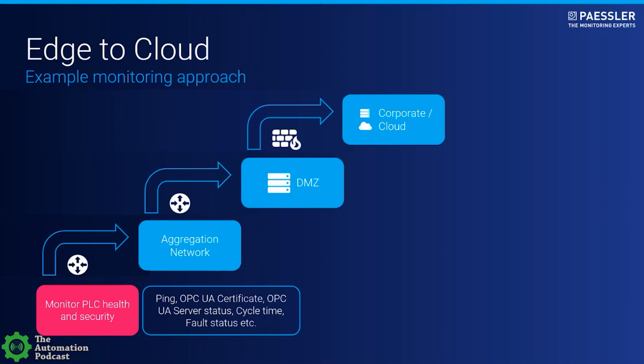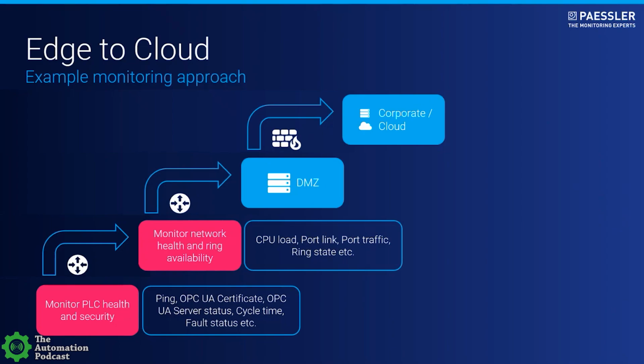Then we go one step above and say, okay, now I know my PLCs are running and everything's fine, how about the network connecting all the things? There we want to ensure the ring topology is up and running, the switches are working fine, there's no traffic overflow. So we can check the CPU load, the port link status, how much traffic is running through, and all these little things to know my network is fine.